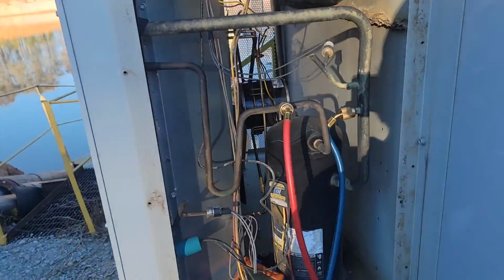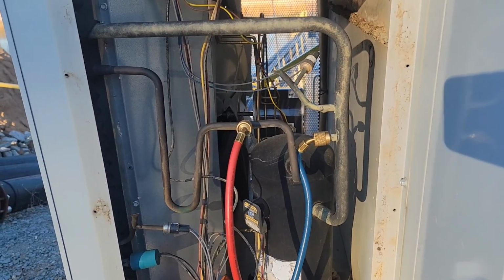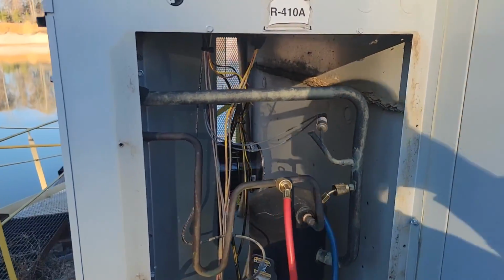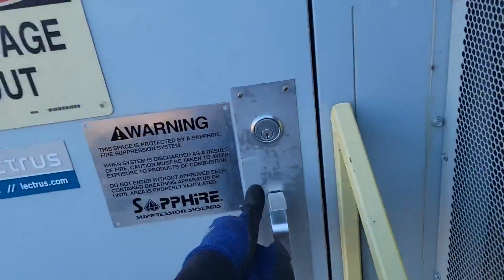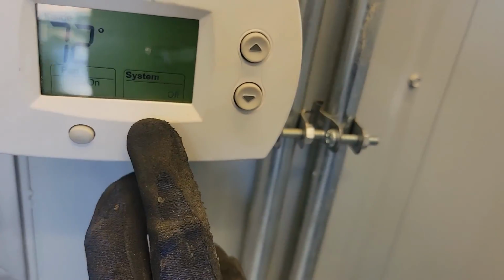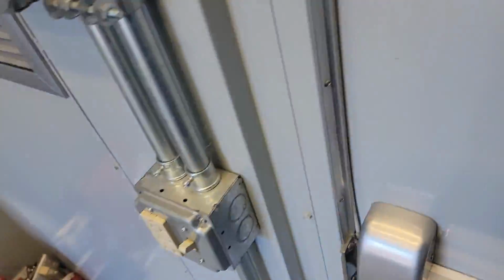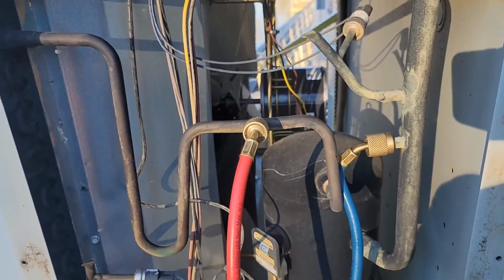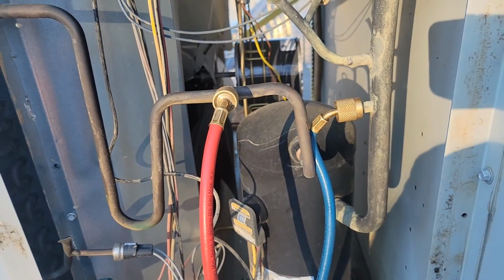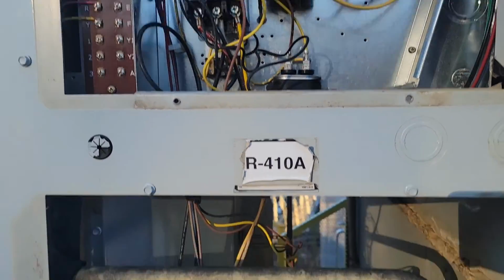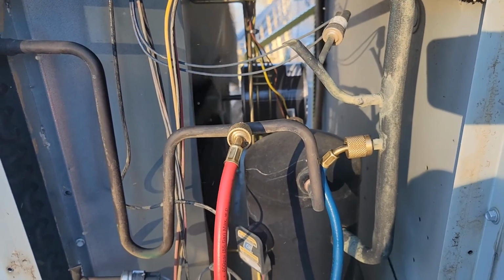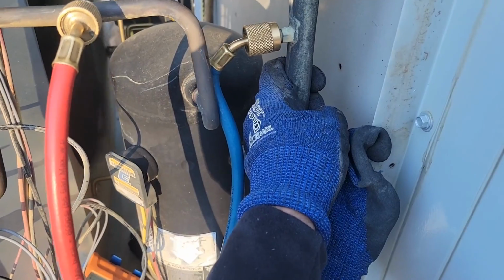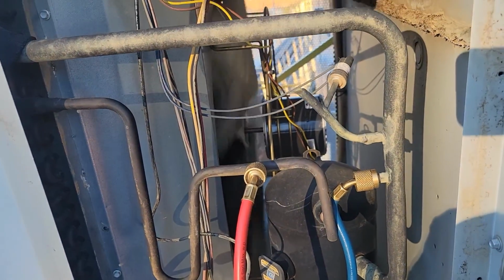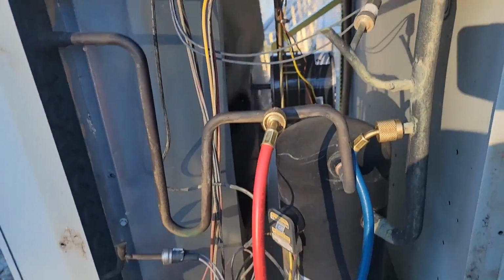Indoor fan kicked on first. Need to check thermostat, make sure it's set. It should be. I'm gonna go check it. It's a little loud in here, so. Cooling. All right. So, heard a click, contactor's buzzing. Outdoor fan is working. Compressor is working. Looks like we made the right decision.